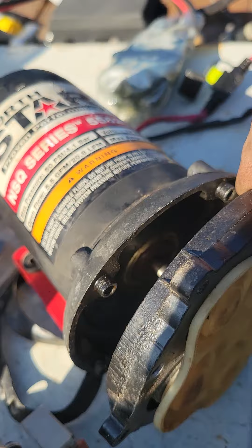So it squirts back here into this void of this housing, and it has pressure on it. There is a gasket that goes on here to seal it. So the pressure has no way to escape, so it blasts it through this bearing and seal into the motor. And that is why I saw the liquid squirting out the wire hole.